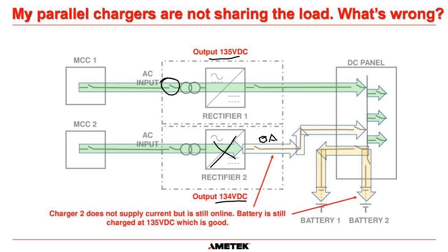Either you can open the AC input breaker on the other charger, and this charger will start; you should see this current go up. Once again, let's use 20 amps here. If you open the AC input breaker on charger A, you should see this go to 20 amps. Or another thing you can do is, near enough every charger system has an equalize button on it. So you would just press the equalize button on charger 2. That would increase the voltage to approximately 140 volts, which is more than 135 volts. So you should see the current increase on that charger. And if that is the case, you know that that charger is good.